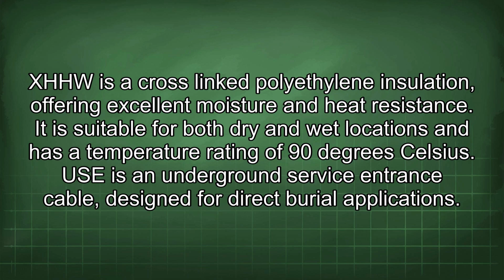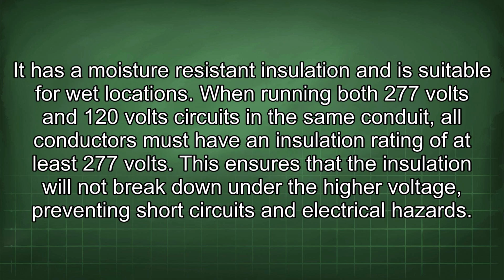XHHW is a cross-linked polyethylene insulation, offering excellent moisture and heat resistance. It is suitable for both dry and wet locations and has a temperature rating of 90 degrees Celsius. USE is an underground service entrance cable, designed for direct burial applications. It has a moisture-resistant insulation and is suitable for wet locations. When running both 277 volt and 120 volt circuits in the same conduit, all conductors must have an insulation rating of at least 277 volts. This ensures that the insulation will not break down under the higher voltage, preventing short circuits and electrical hazards.